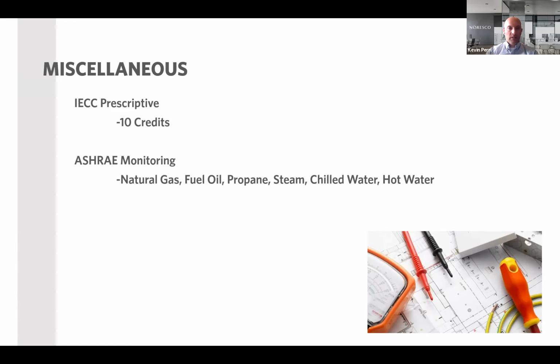The other miscellaneous item is ASHRAE monitoring. ASHRAE calls out that not just the energy stuff that we were looking at before from the electrical section, you also have to monitor other fuels: natural gas, fuel oil, propane, steam, chilled water, and hot water. So that is an additional monitoring item in ASHRAE that you have to do.